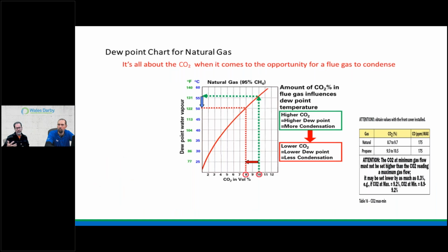So again, the dew point, right? We mentioned the dew point, and I have this range here, and I'm focusing on that 8 to 10, the red line, green line, and you see that swooping red, the dew point line there. So you can have a high dew point setting, but you're not condensing until you get 130 and lower. And then if you go too low, now you're waiting to condense because you're setting your parameters maybe closer to that 8 line, okay? So therefore, I'm not going to start condensing. I'm below 130, I'm below 127, I'm hitting 125, and I'm still not condensing because of the way I set up my gas valve.